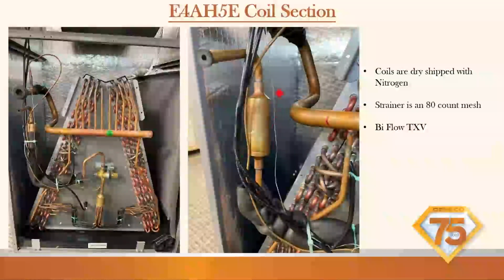Here's a good picture of that strainer. That's all that is. It's like a little filter dryer in there. So technically, if you had a plugged strainer, you could add a 3/8 external bi-flow filter dryer on the outside of the coil and straight pipe that. So keep that in mind. You don't necessarily need that back in there. Of course, it's always good to put in OEM product, but if you're in a pinch, you can just add a 3/8 filter dryer on the outside.